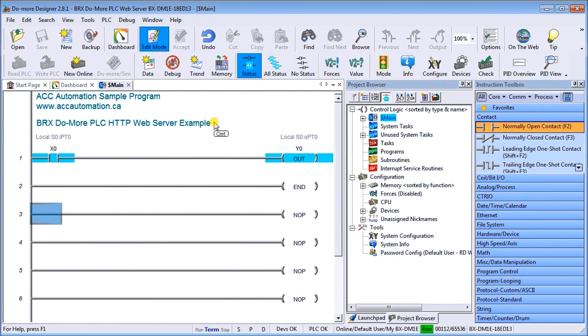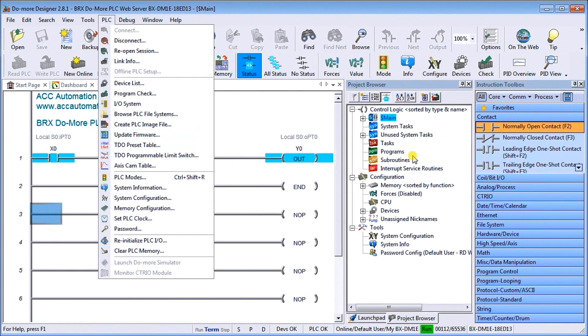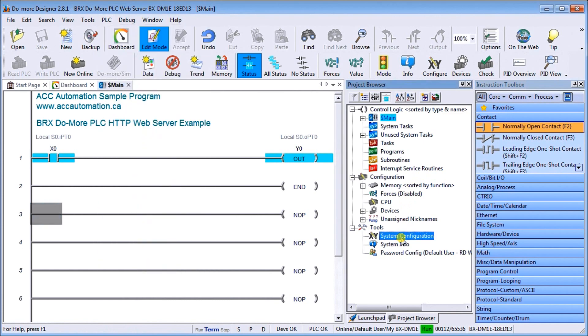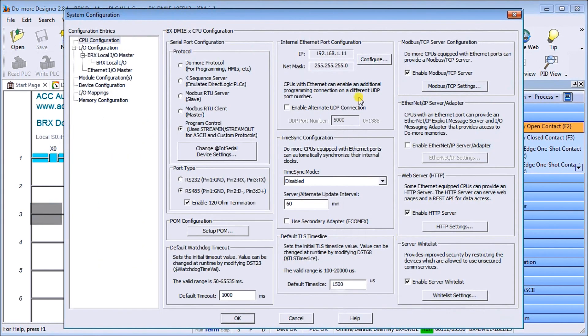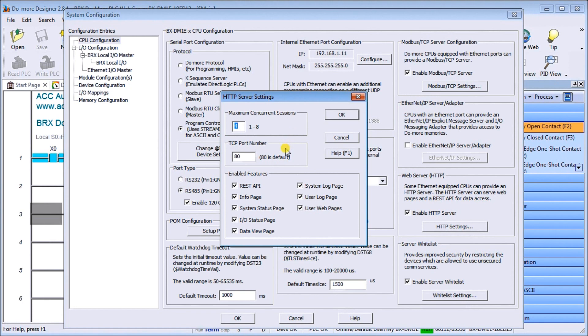Next what we'll do is actually enable our HTTP web server. We go PLC and then system configuration, or under tools, system configuration - that'll get us to the same location. We go down to web server HTTP, ensure that's enabled, then click on HTTP settings and we'll see that we have the maximum concurrent sessions is four. What that means is that we can have four web browsers pointing to our location.